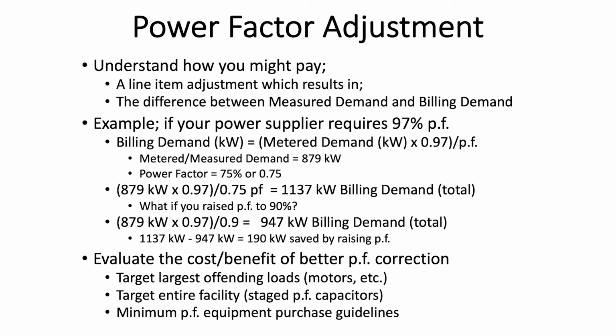So I have somebody come in, they do a power factor correction study. And they say, okay, we think that we can get your power factor to 90% by putting in some correction capacitors. So what does that do for me? The 879 times the 0.97 trigger divided by the 0.9 new power factor means I'm paying for 947 kilowatts of billing demand. So what did I just do? By putting in power factor correction, I drop my monthly billed demand here, if it's always around 879, by 190 kilowatts. At $10 a kilowatt, that's basically $1,900 a month.